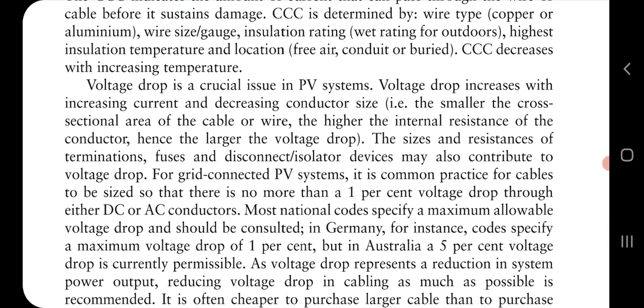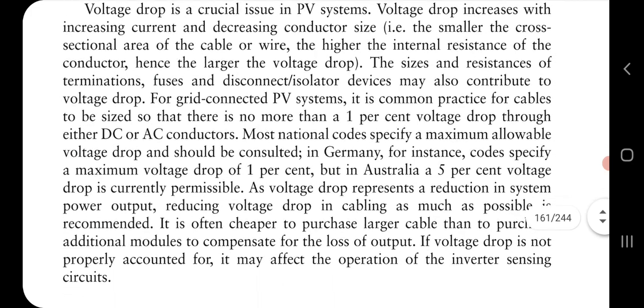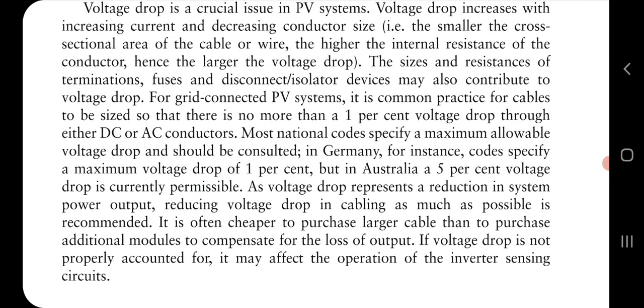So the size and resistance of terminations, fuses and disconnector devices may also contribute to the voltage loss. For AC or DC cable, whatever it is, there is some voltage loss due to the internal resistance. Different countries have set different specific codes. For Germany, a 1% voltage drop is considered, whereas in Australia 5% voltage drop is permitted.